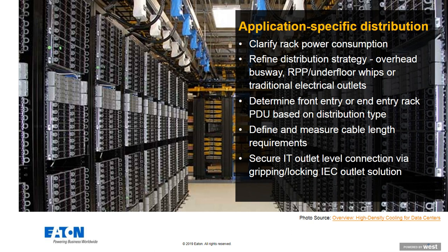Next thing you need to do is refine your distribution strategy. That's looking at how the power is going to get out to the racks of equipment. Very common today, you'll see overhead distribution via a busway type system, where you have a busway running with power drops that drop over the enclosures. But you also still see RPP and more of the traditional underfloor, where you have a raised floor and you run your power underfloor from an RPP or a PDU, and those whips would come up underneath the floor. So it's a difference between does the power come overhead or underfloor, and then how does it connect into the PDU once it gets inside the enclosure.